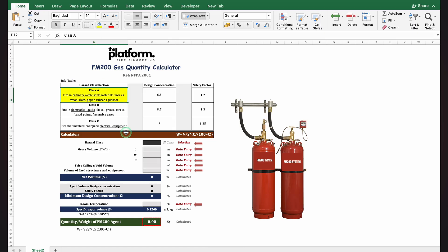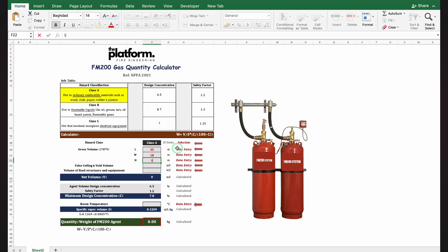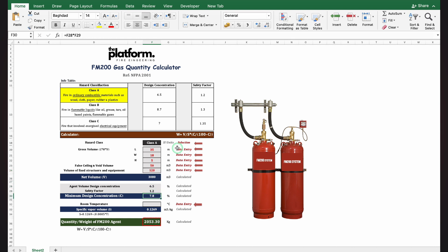For example 2, we start by choosing the hazard class. The library hazard is considered ordinary combustible material, so we choose class A. Now calculating the net volume — starting by the room volume, entering the data as mentioned in the example, then the false ceiling volume and the fixed structure volume. This gives us the net volume required to be protected by the FM 200 gas.